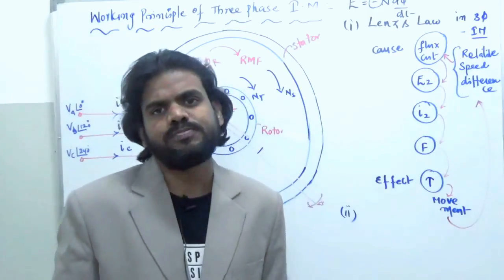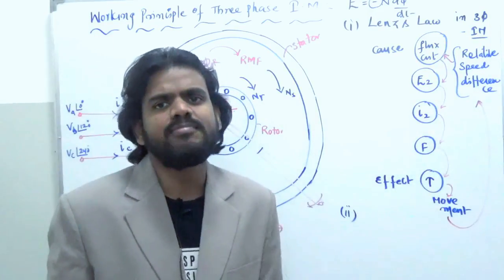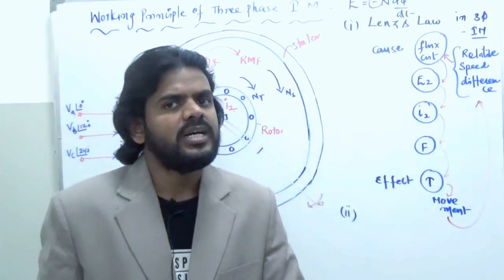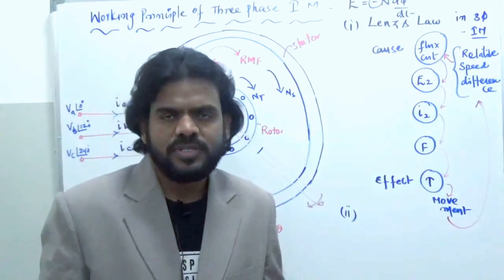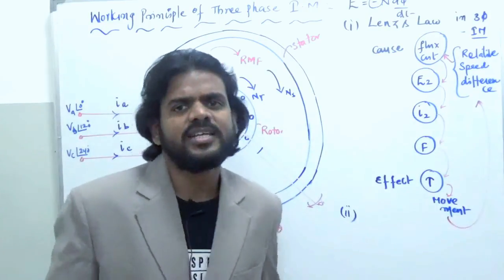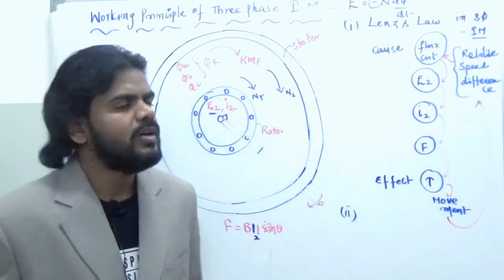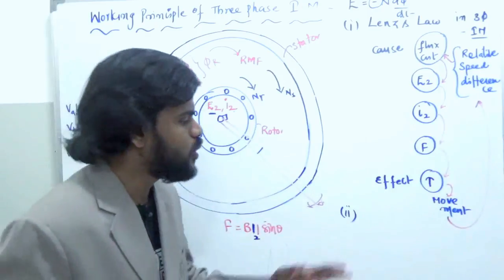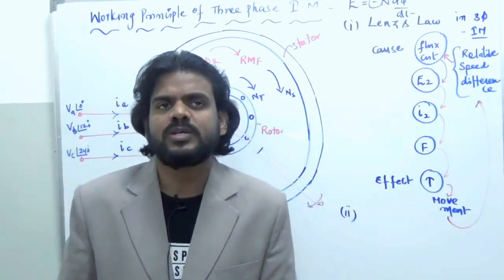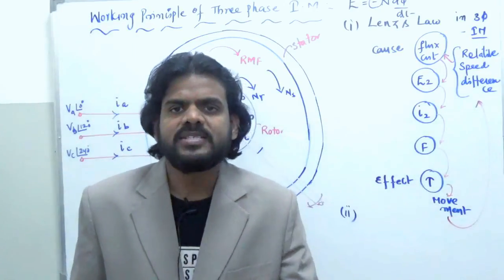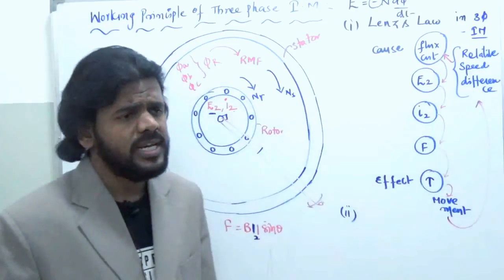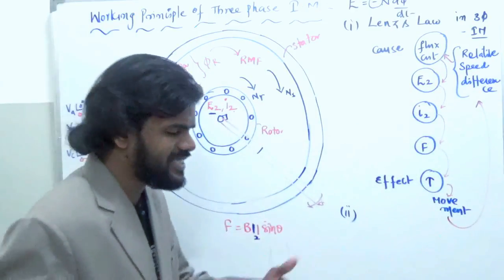By which there is no movement, which means the rotor stops. So what happens if the rotor speed equals the synchronous speed? The motor simply will not have EMF induction because the relative speed is zero — EMF is zero, current is zero, force is zero, torque is zero, and movement stops. This is the second important point: if the rotor speed equals synchronous speed, the motor doesn't function.